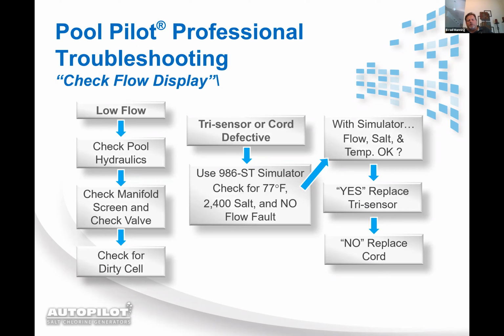Check flow. You're going to troubleshoot just like you would any other system. You're going to plug your 986-ST in to see if the flow message goes away. If you plug your tri-sensor simulator into the unit and the flow message goes away, that means there's not an issue with the power supply, and you need to be troubleshooting outside the power supply, via the manifold or actual flow issues. So if the message goes away, you're going to check your debris screen.